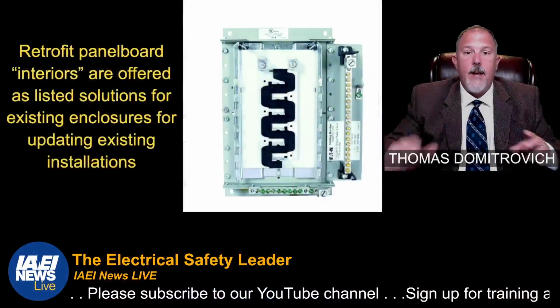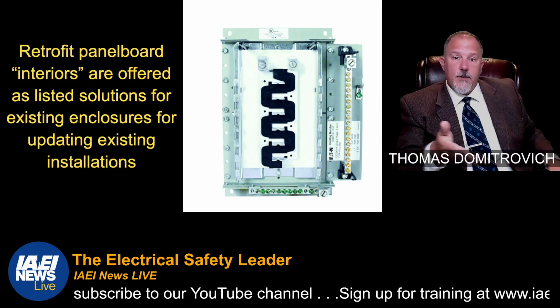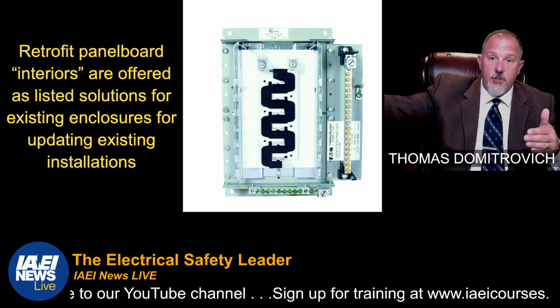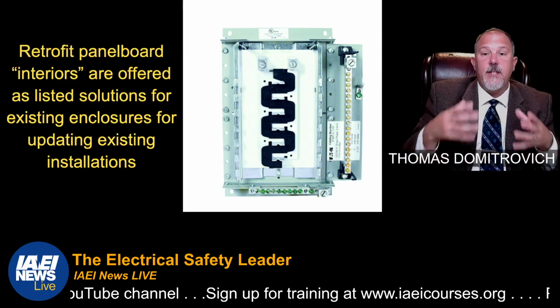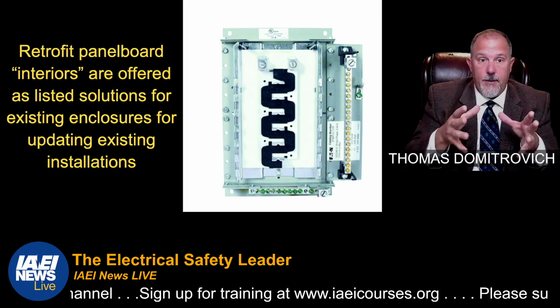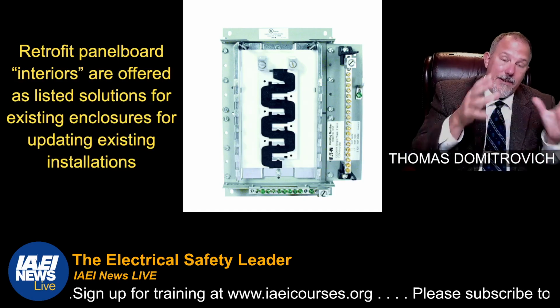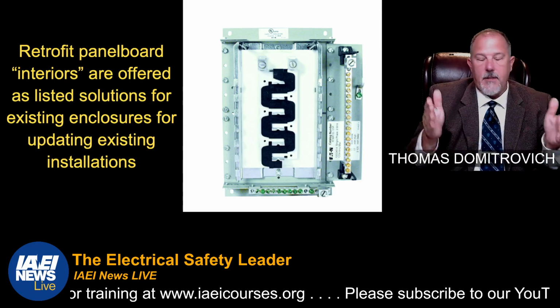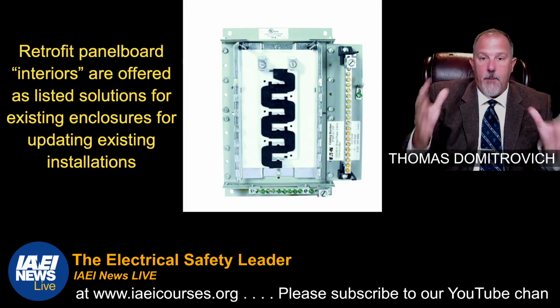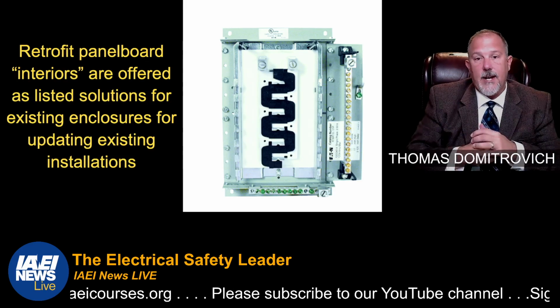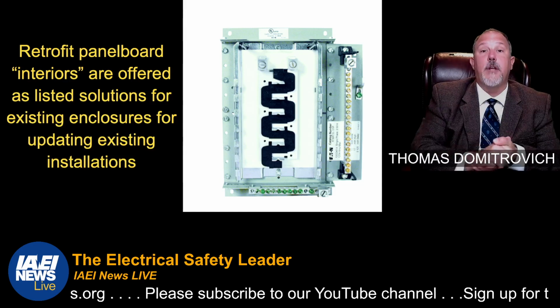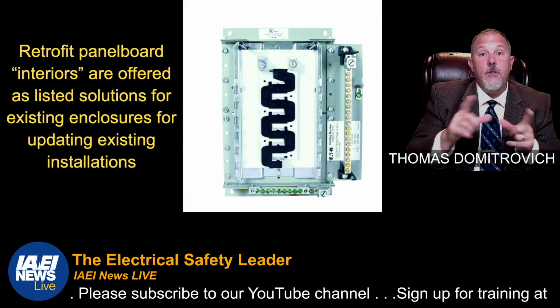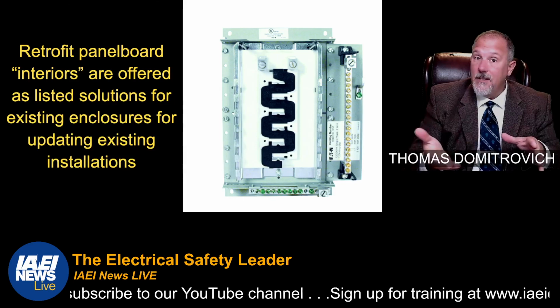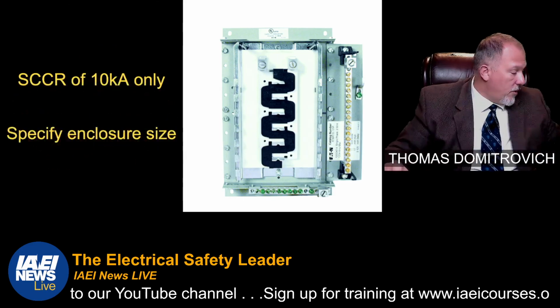All right, and now, retrofit panelboard interiors. So if you have an existing enclosure out there, there are manufacturers that make interiors that will go inside of an enclosure. You've got to come up with the dimensions of the box, and they'll tell you how many breakers you could put in there, and those calculations are based upon bending spaces, etc., which are a part of the code.